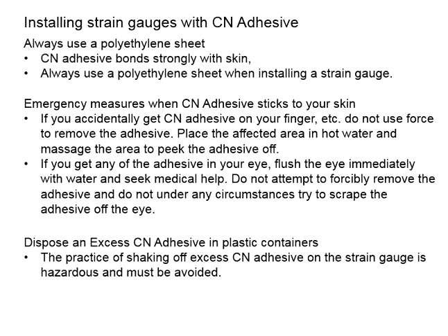Now, when you have excess CN adhesive and the area is flooded with it, this may increase the tendency of the CN adhesive to accidentally come in contact with your fingers or hand, and this can be hazardous. If you have accidentally stuck the CN adhesive to your hand after removing the polyethylene sheets, while removing your hand from the strain gauge, if your hand is already stuck with CN adhesive together with the strain gauge, this might also lead to damage of the strain gauge. You need to be extra careful on that.